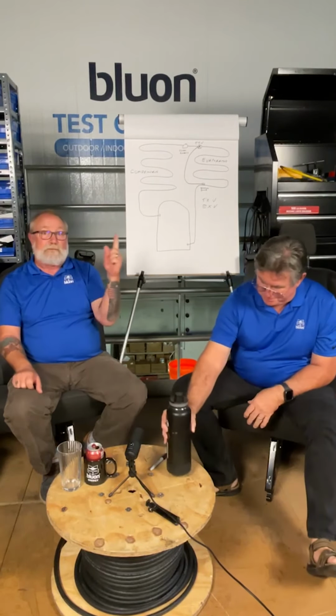How do you know thermal overload is open on a compressor? Compressor won't run. That's good. That's a first indicator. Second indicator is you can fry an egg on it. Third indicator is actually take your own meter out and ohm the windings. If the compressor is cold to the touch or cool, meaning that you can put your hand on it for more than 5 seconds, that's cool to the touch. Now you ohm the windings. If the windings are still OL, then chances are you need to change the compressor.